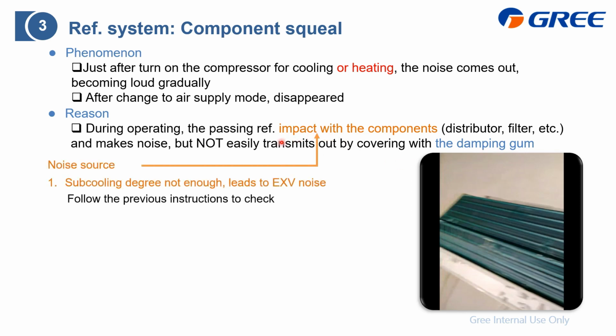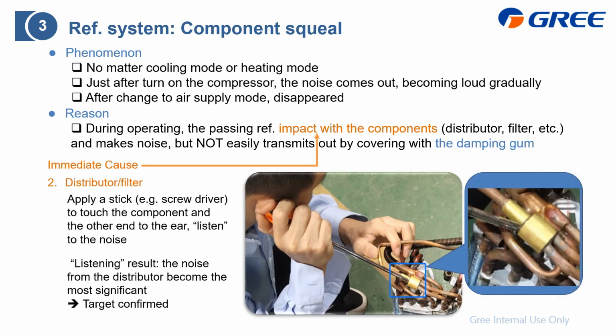So first we need to identify which is the noise source, similar to the EXV. First is to check the subcooling degree, whether it is enough or not. If it is not enough, it is always due to the EXV making the noise, and you can just follow the previous instruction to check. Except the EXV, there are also the distributor and filter inside the indoor unit, and these two make noise.